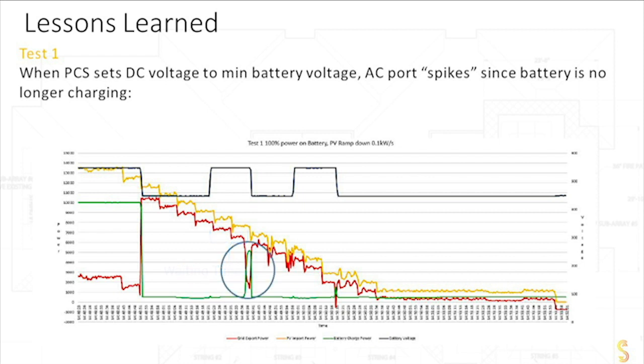And so it does, and you see that green spike of the battery trying to charge. Well, guess what? It tries to charge, it ramps up, but the red line dips way down low. Because obviously if we only have so much supply from the solar, and the battery tries to gobble up a lot of it, the red line's going to drop close to zero, and once again, we're in danger of importing from the grid, which is not allowed. And the inverter sees that, and it repeats the whole process all over again.